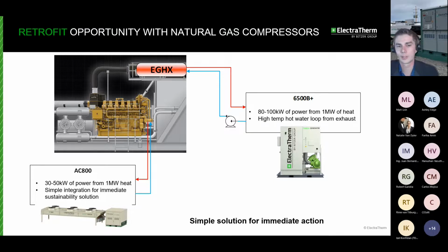So some good examples, I've looked at some sites recently where they have enough heat for 150 kilowatts just from the exhaust of a single engine. Some larger engines might be capable of powering 2 of our 6500Bs, which is important. They can be operated together and also produce, say, 300 kilowatts at those potential sites. The benefit of running multiple units together and of our screw expander is that we're able to operate at a much higher turn down than a lot of other technologies. So this equipment can operate at a 10-to-1 turn down. So if you look at it from the ways of conventional power generation, about 10% rated output, that means that we're able to make power and cool equipment through a wider range of processes.